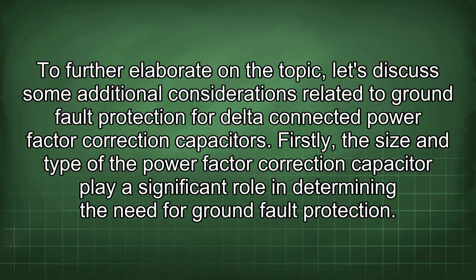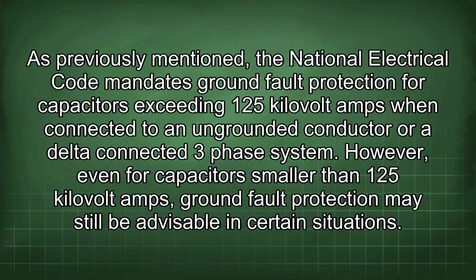To further elaborate on the topic, let's discuss some additional considerations related to ground fault protection for delta-connected power factor correction capacitors. Firstly, the size and type of the power factor correction capacitor play a significant role in determining the need for ground fault protection. As previously mentioned, the National Electrical Code mandates ground fault protection for capacitors exceeding 125 kVA when connected to an ungrounded conductor or delta-connected three-phase system. However, even for capacitors smaller than 125 kVA, ground fault protection may still be advisable in certain situations.